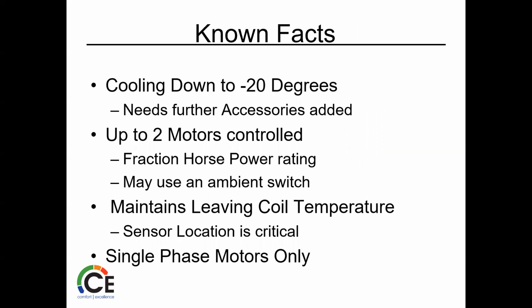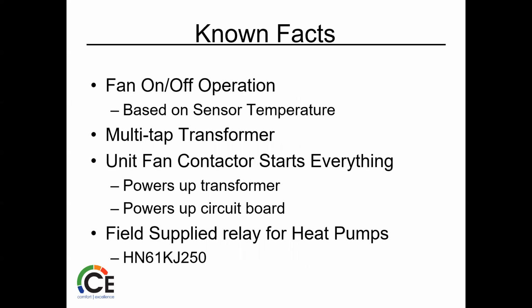Cooling down to -20 again. Does need some extra accessories. You control up to 2 motors with this one, so you can do both fan motors if you have it, or if you have multiple ones, at least you're shutting 2 down. Maintains the leaving coil temperature. That's where the sensor is located. Again, critical location. Single phase motors only. Fan on and off operation based on that sensor temperature. So again, that location is critical.